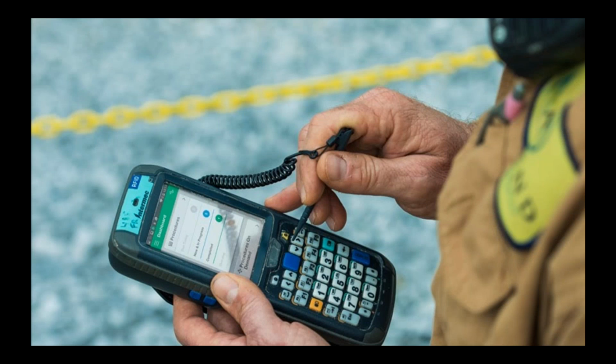Just a quick story. We had an air compressor in our Decatur plant. And the operators programmed it properly. We had good limits in. The operator went out, did his round. He typed in a pressure, I think it was 40 PSI from the lube oil system, and had an alert. The IntelaTrac, the mobile device, said alert, pressure too high. He didn't know, and it just said, put in a work order, contact supervision. We could put in notifications right there on the handheld device.